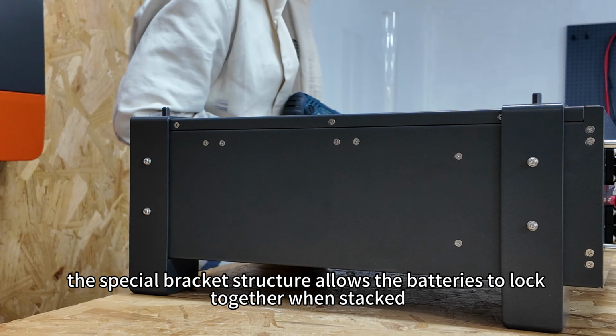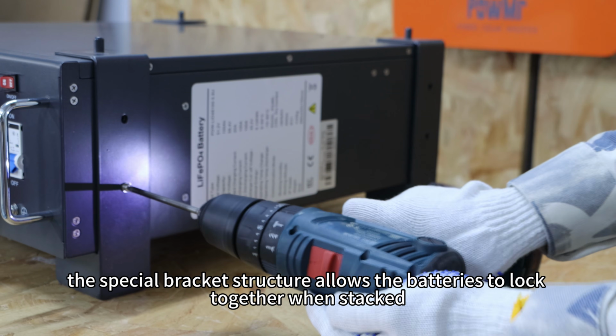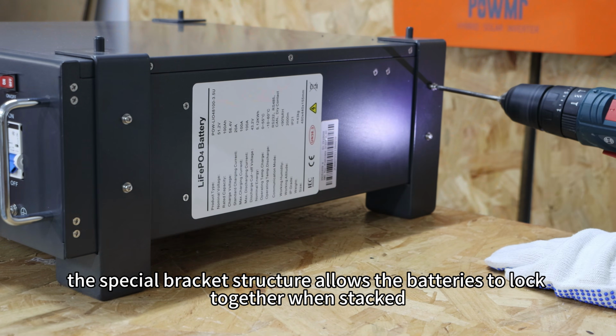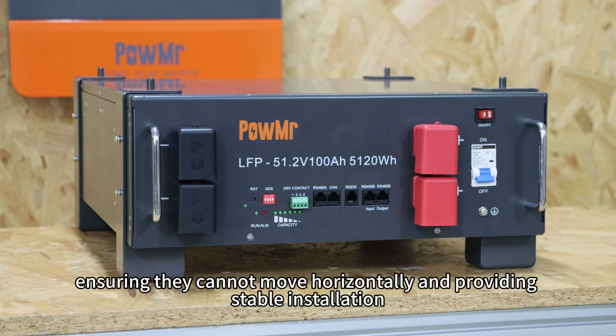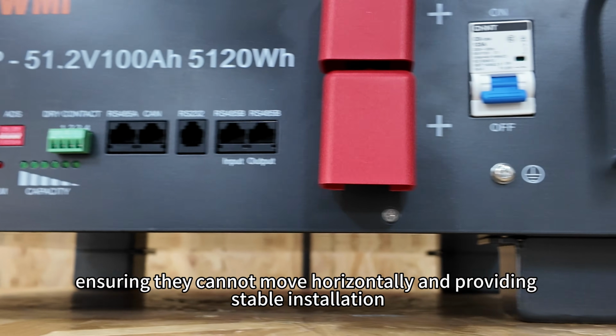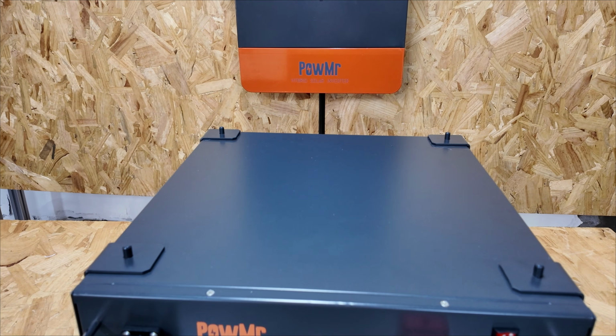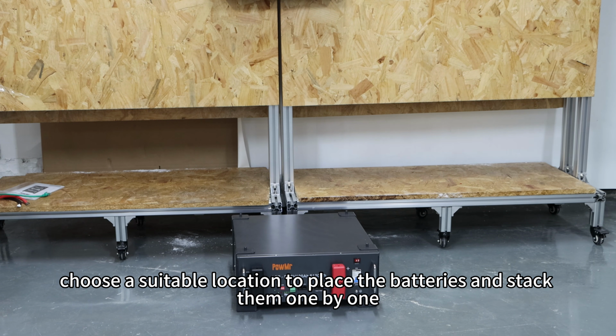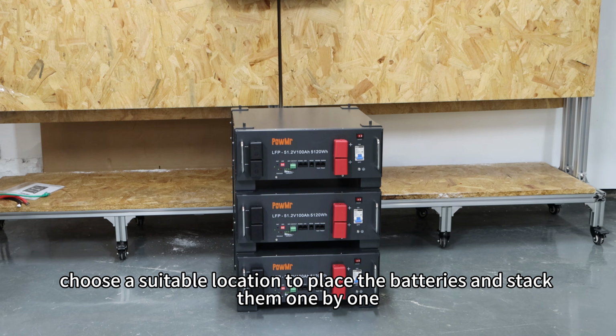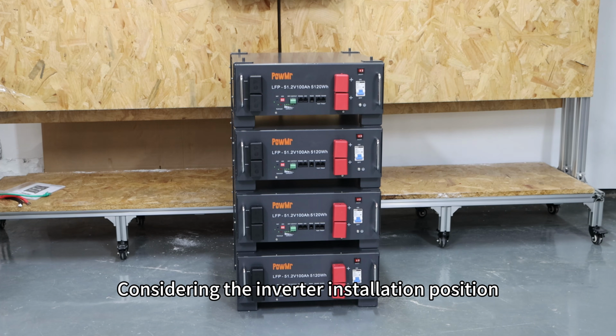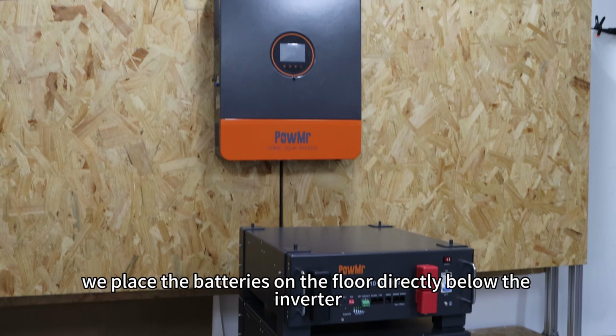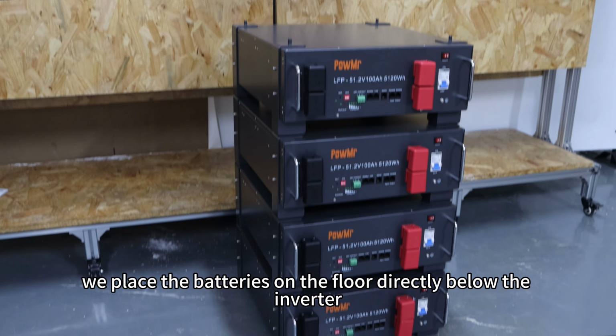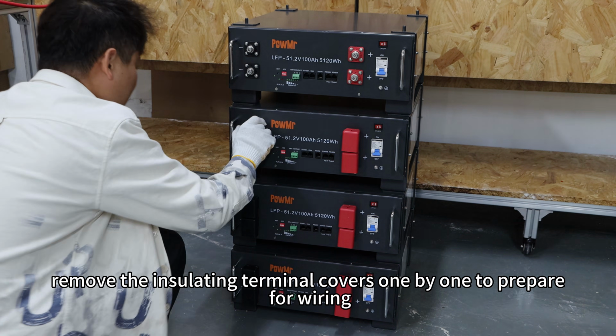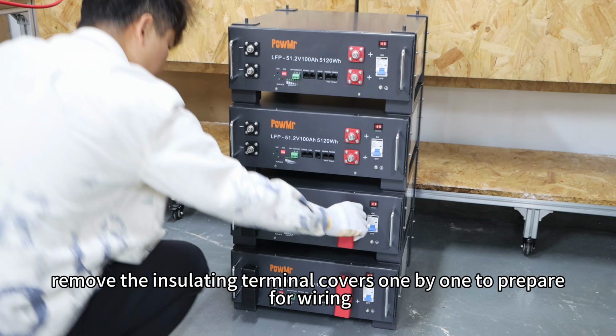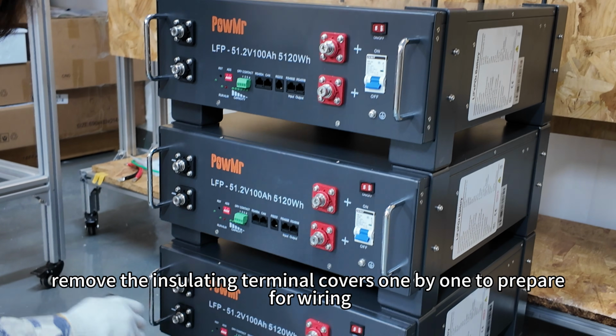Once installed, the special bracket structure allows the batteries to lock together when stacked, ensuring they cannot move horizontally and providing stable installation. Next, choose a suitable location to place the batteries and stack them one by one. Considering the inverter installation position, we place the batteries on the floor directly following the inverter. After positioning the batteries, remove the insulating terminal covers one by one to prepare for wiring.